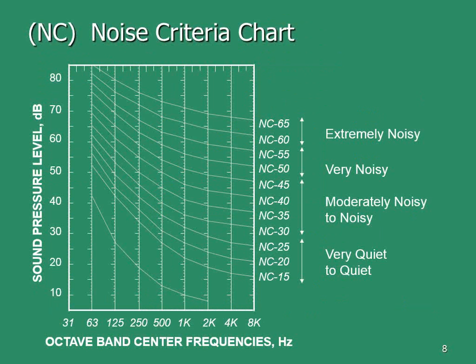You've run into the NC, or noise criteria, charts quite a bit. Basically, these are equal loudness curves. So you pick a point anywhere along the curve, like 8,000 hertz at NC 25 is a level of about 26 decibels, and that's equally as loud as 59 decibels at 63 hertz.